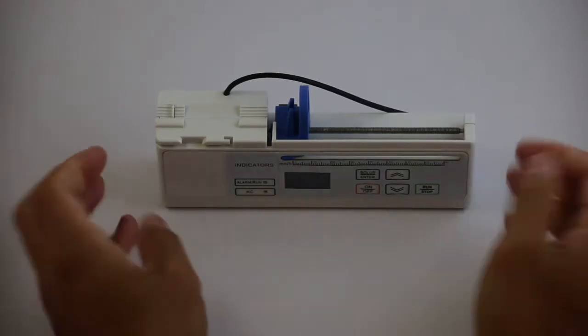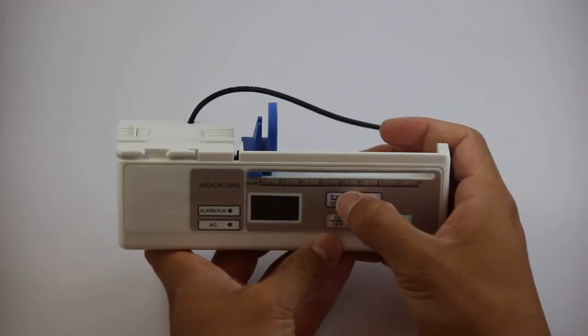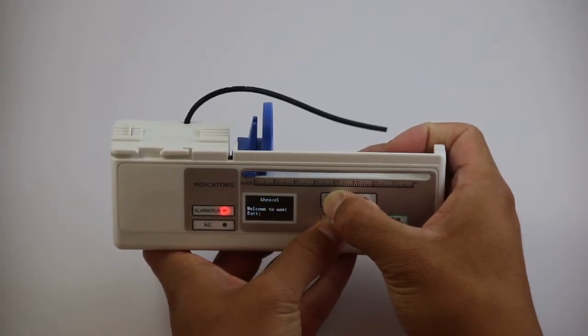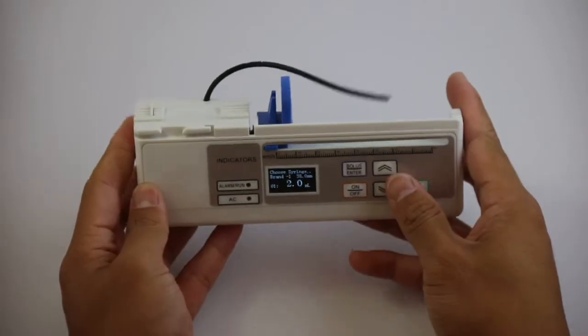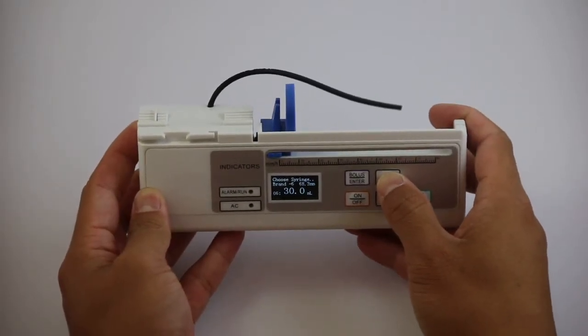To begin, ensure the machine is turned off. Whilst off, press and hold the bolus enter button while simultaneously pressing the on/off button to turn the unit on. This will initiate the settings mode where the syringes can be calibrated.